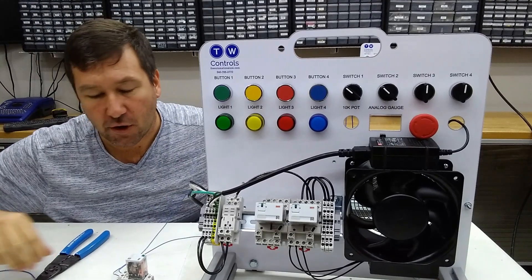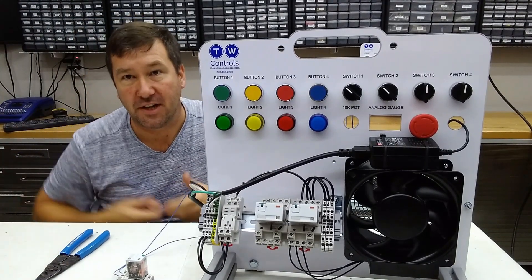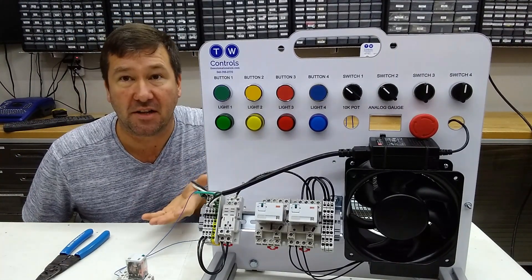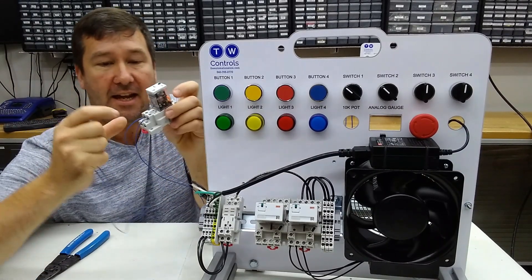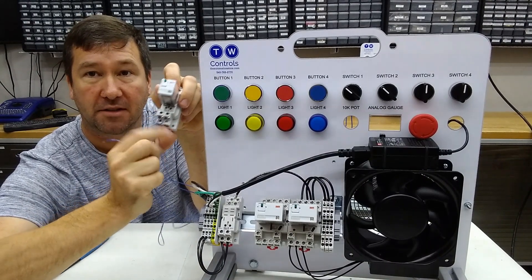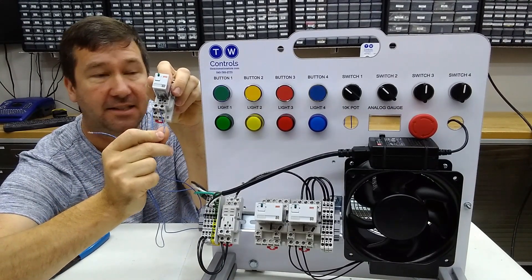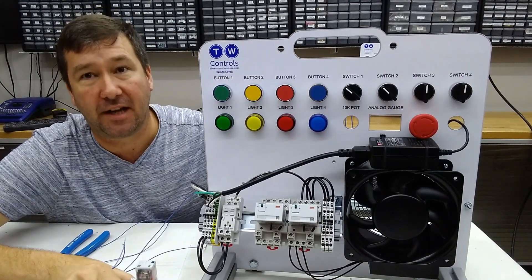Now let's take it a step further. While we have it just like it is, let's say we wanted to know that this relay was energized on the front of the panel. To do that, we can simply take a wire from across the same coil where we're connected here to one of our indicator lights.